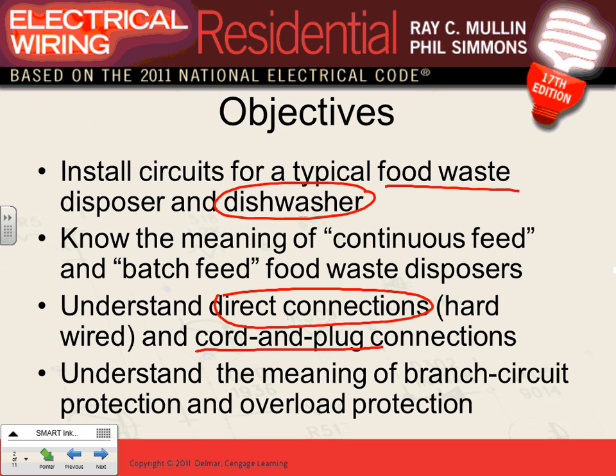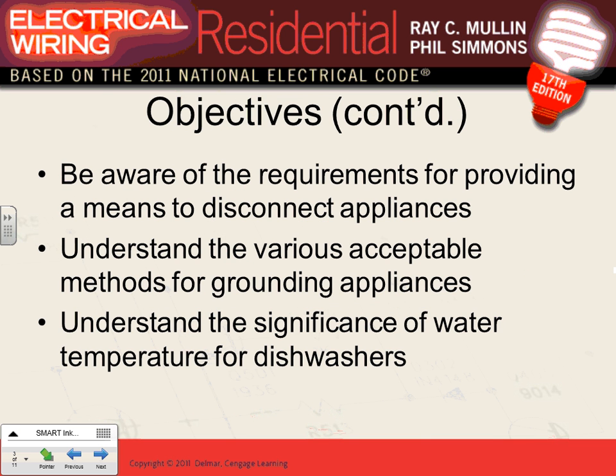They all come with overload, guys. Garbage disposal, all equipment comes with an overload. So if you overload this equipment, it will trip and prevent you from energizing that piece of equipment for a while until it cools down and comes back. That's overload. We talked about overload for motors, protecting you from overloading the circuit. Means of disconnect, I can't emphasize disconnect enough. Every time you have an appliance or a machine or equipment, in the back of your mind, I need to provide a disconnect. A disconnect could be as easy as a snap switch for fractional horsepower motors and single phase motors, or a circuit breaker within 50 feet, or, as we move forward into commercial industrial buildings, a NEMA heavy duty, horsepower rated disconnect switch on the wall. Can I have a thumbs up for these?